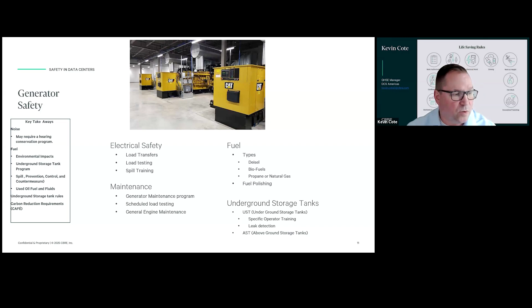You have to have a structure that tracks all your runtime throughout the season. Also, if there's a high load on the overall system, like on a 100-degree day, you may be asked, or you may join a program, to reduce energy costs by coming off the grid at certain high-demand times. That may also activate your generators. It'll be a planned event where the utility says, we're going to have high demand on the system, can you please switch from our system to yours.